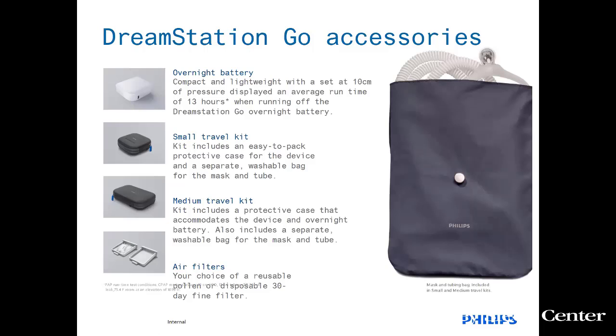But this battery, depending on what pressure you're using and depending on the elevation, you can get up to 20 hours of use out of this battery off of one charge, and it takes 3 to 4 hours to charge it up. But the average runtime, if you look at the majority of the percentage of where people's therapy pressures are at, the average runtime is 13 hours. There are small and medium-sized travel kits. You would need a medium-sized travel kit if you have the battery, because it does attach to the PAP device itself, increases the weight by 1.5 pounds, but it also increases the actual footprint of the unit by about 60%. So you need a larger travel kit for that one.